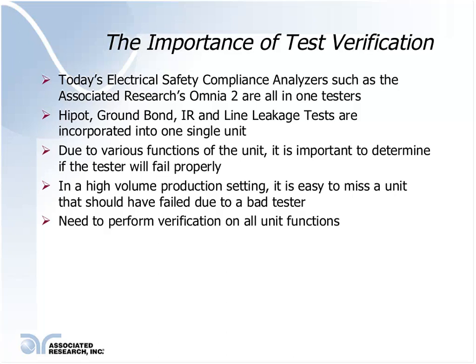Nowadays, due to the various functions of the units, it is very important to determine if the tester will fail properly when a regulated test value has been exceeded, or in a high volume production line setting, it can be easy to miss a unit that should have failed due to a bad tester.